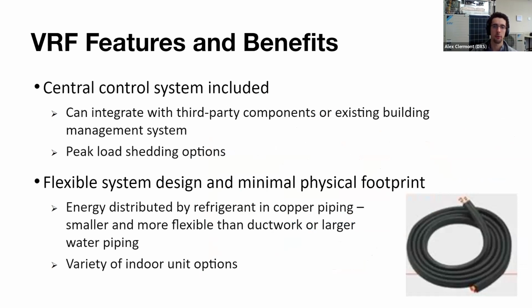Since we're on the topic of VRF, we thought we would talk about some of the pros and cons of VRF. Oftentimes we see these VRF systems installed in both existing and new buildings. In terms of controls, they're often integrated into a central building management system, and VRF manufacturers make this process quite easy by allowing control systems to talk seamlessly with the VRF system. In terms of installation, refrigerant piping is quite easy to fit through existing buildings, so VRF systems are quite ideal for retrofit applications. If you wanted to run water piping or ductwork throughout the building, that would take up a lot more space than running those smaller refrigerant pipes.